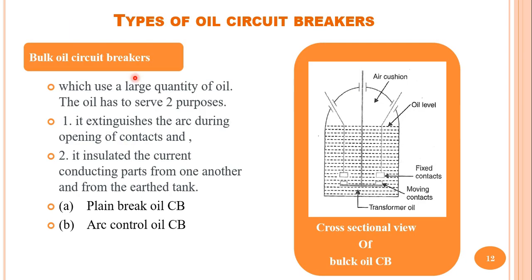Oil circuit breakers are mainly classified as bulk oil circuit breakers and low oil circuit breakers. In bulk oil circuit breakers, a large quantity of oil is used and it serves mainly two purposes: it extinguishes the arc during opening of the contact, and it is used as an insulating medium — insulating the current-conducting parts from one another and from the earthed tank. The two types of bulk oil circuit breakers are plain break and arc control oil circuit breakers.